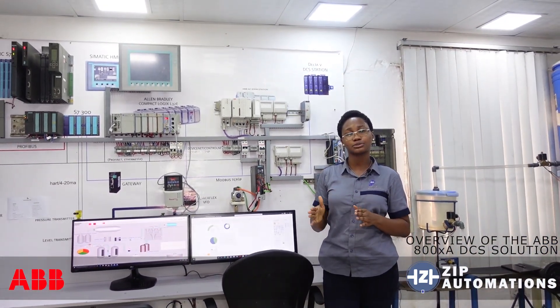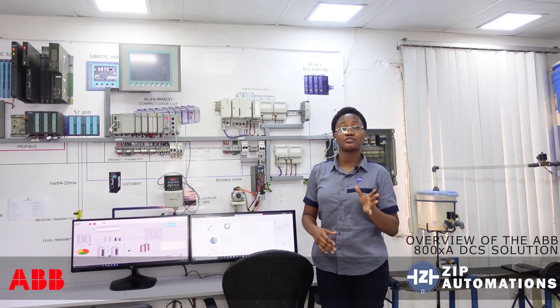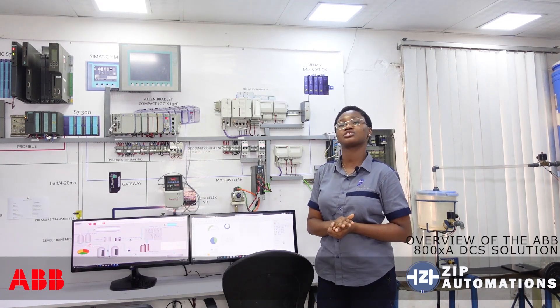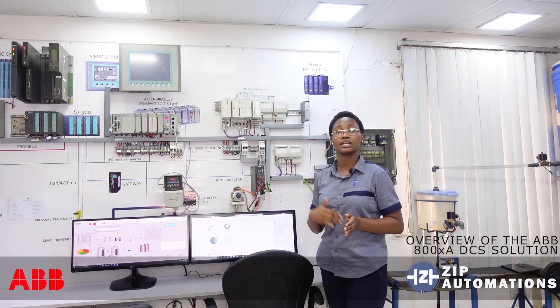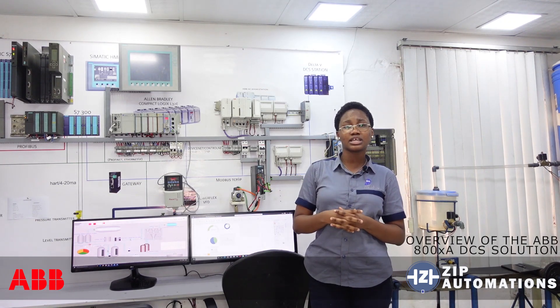This system also allows for redundant controller configuration, in the sense that you can have multiple controllers of the same type set up and programmed to do the same thing — with one controller performing the main action, and in case of failure, it quickly switches control to the next. The same can be done for IO modules, with multiple modules set up to do the same thing, and in case of failure of one, it quickly switches over to the next.